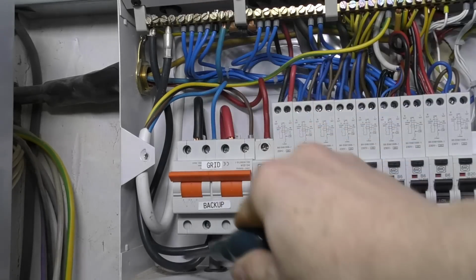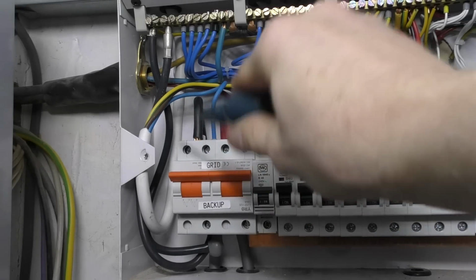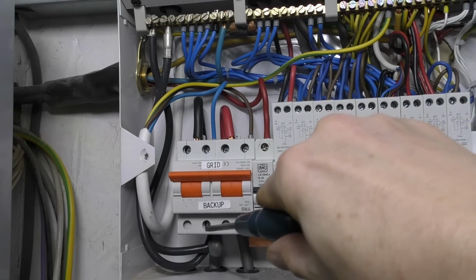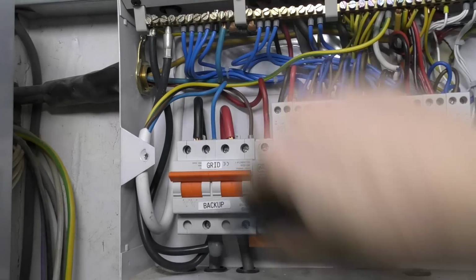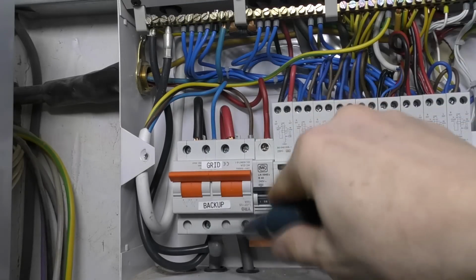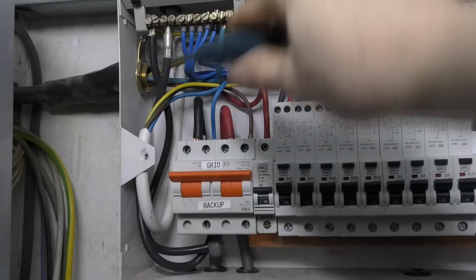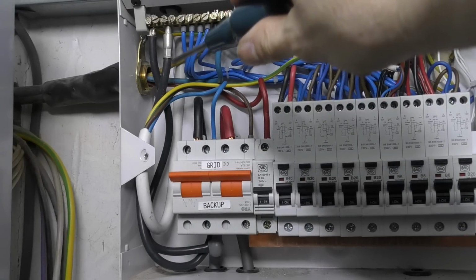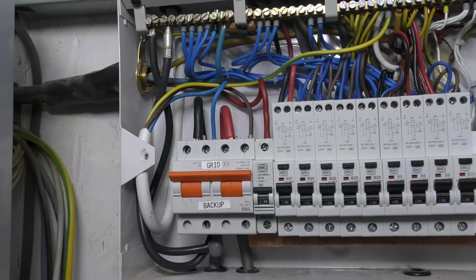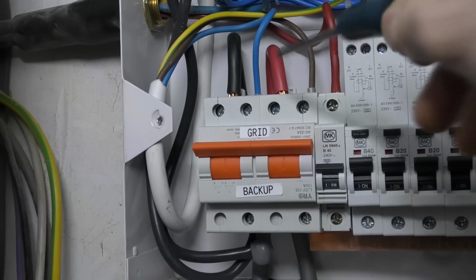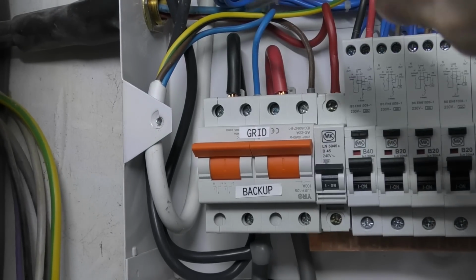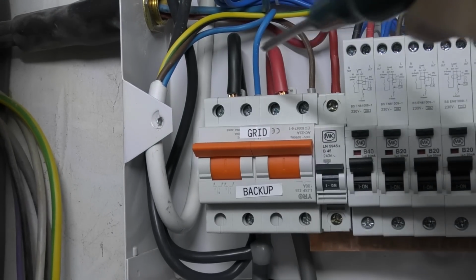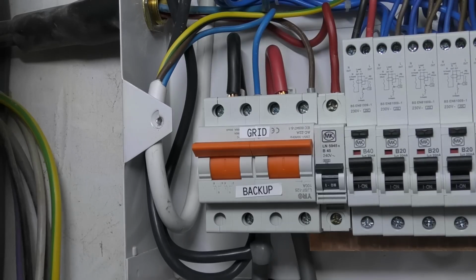I had this double heavy-duty tail, which I think may have actually been from the original dual RCD installation, so I just used that to replace the neutral bus bar. So there's 2 wires purely because it was just a thing that I had to hand that obviously had suitable current carrying capability. So here the red and black are the incoming tails from the meter, and then these brown and blue are the connections to the 32 amp inlet, and then this goes out to the rest of it.